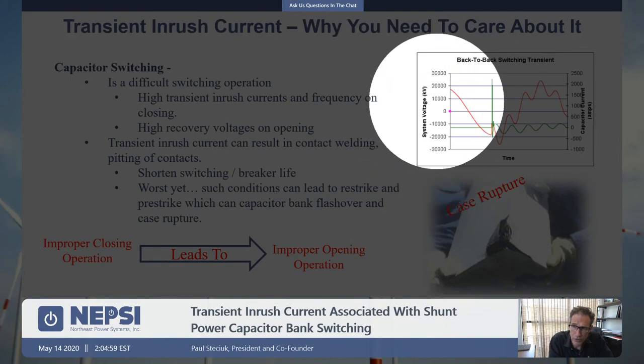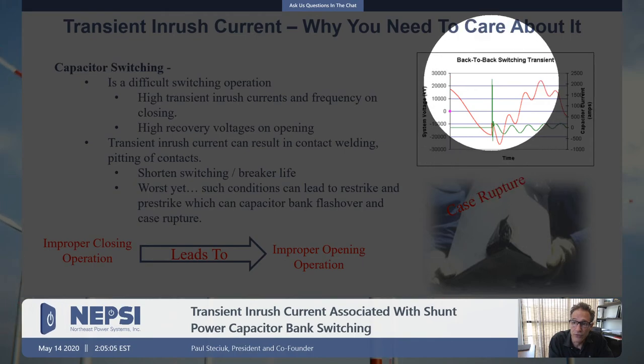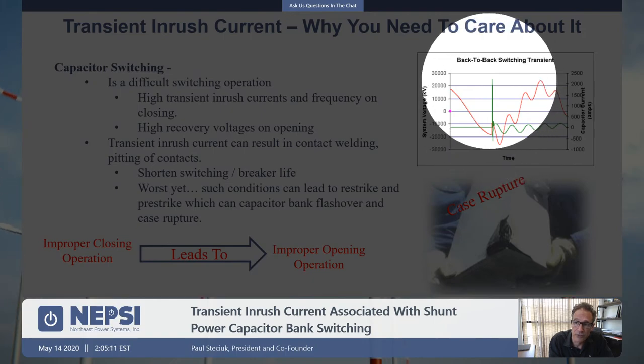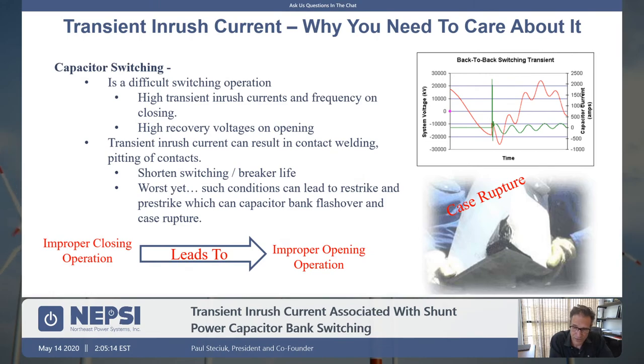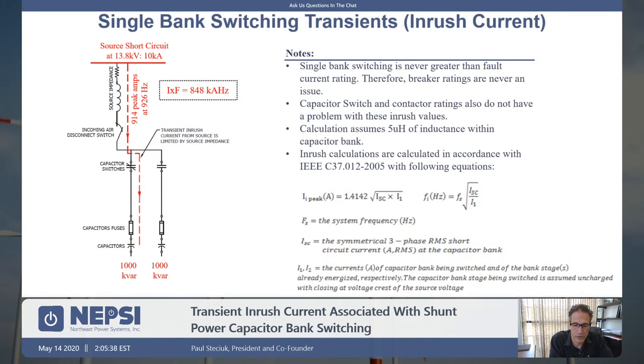Here I show a quick back-to-back switching operation. The red curve is the voltage and the green curve is the current. On closing of the vacuum switch, there's a very high inrush current. That inrush current can be tens of thousands — even 100,000 amps — if you have not included the right amount of inductance. We'll cover how to calculate the transient inrush current and frequency, and how to compare those against the switch rating.